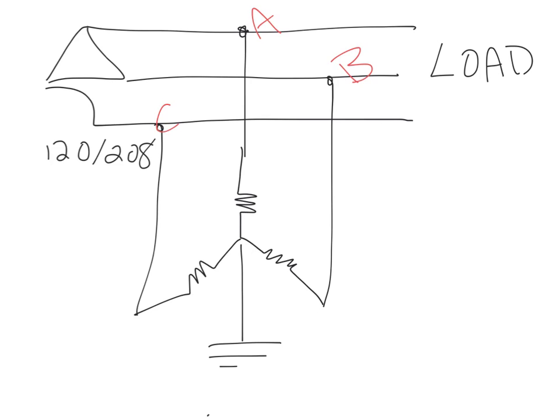Those are all lines which give us line voltage. Now, traditionally Delta-connected secondaries aren't necessarily 208, some are, some aren't, but this setup is considered 120/208 because we are going to see, in a normal circumstance, a phase voltage across each one of these lines to neutral.